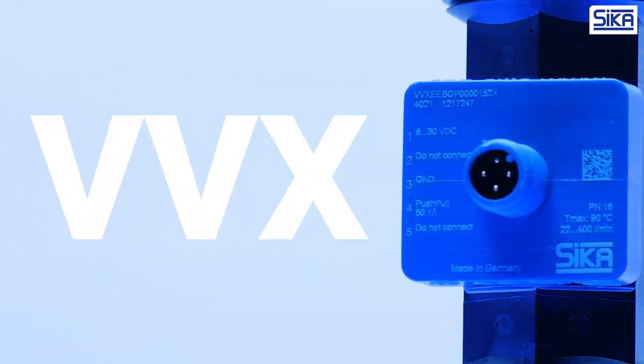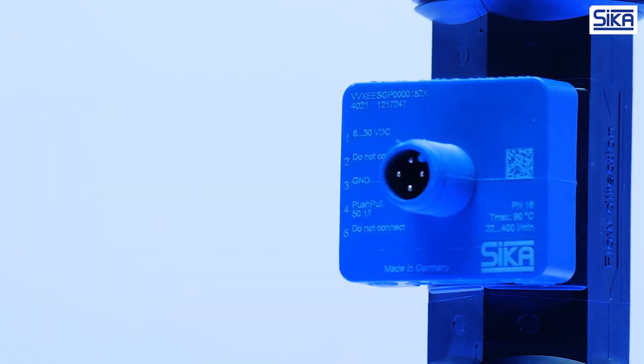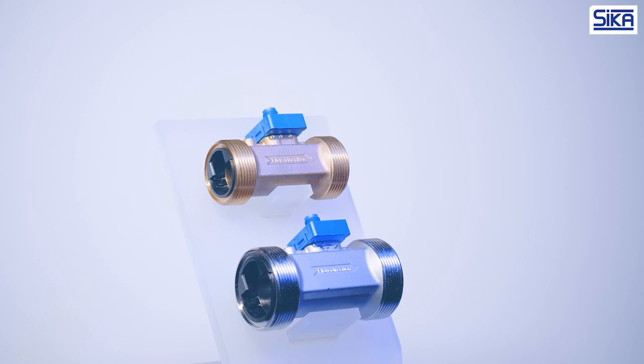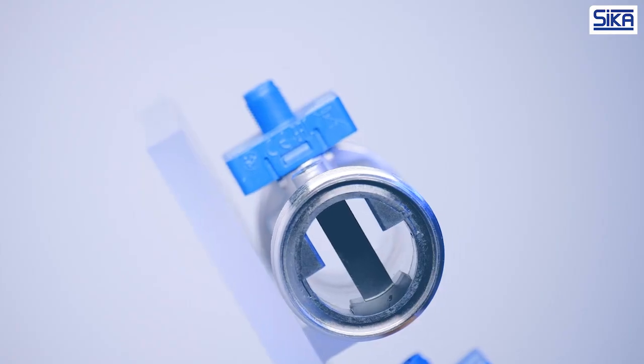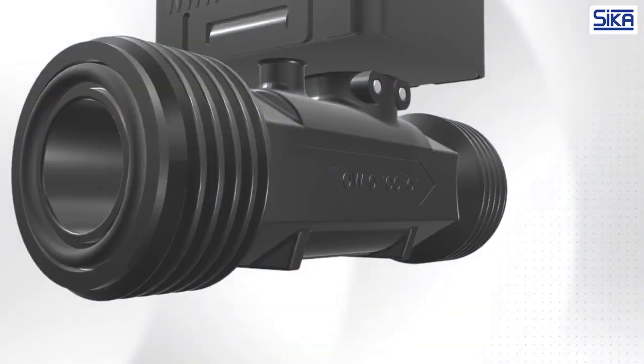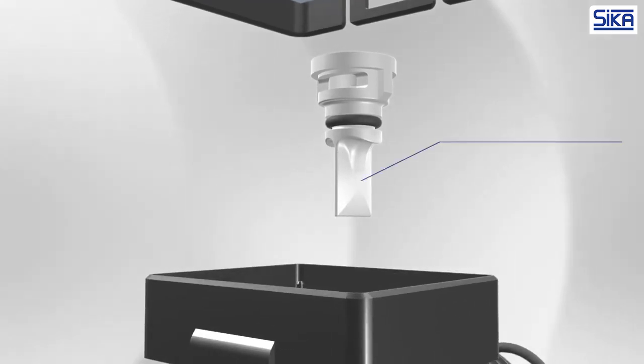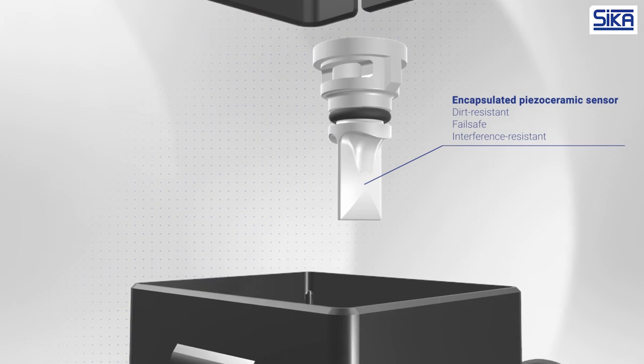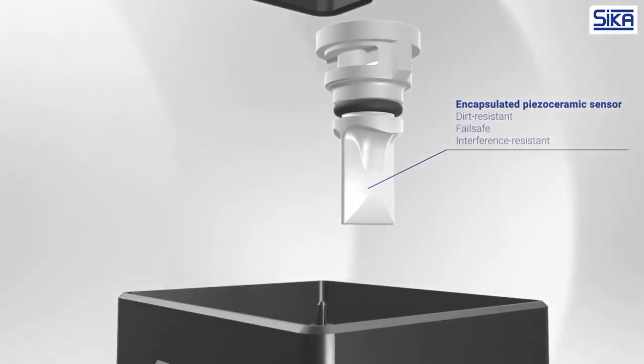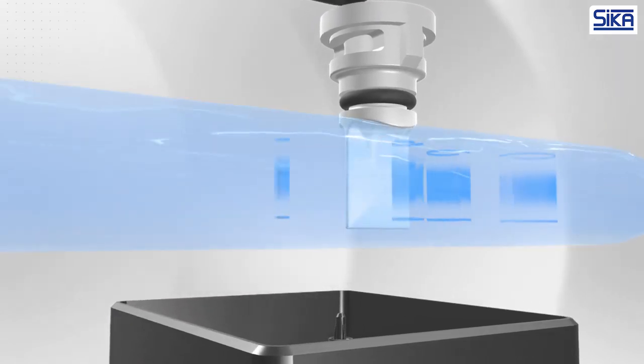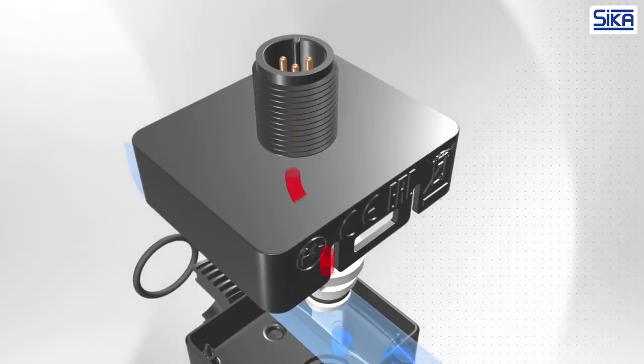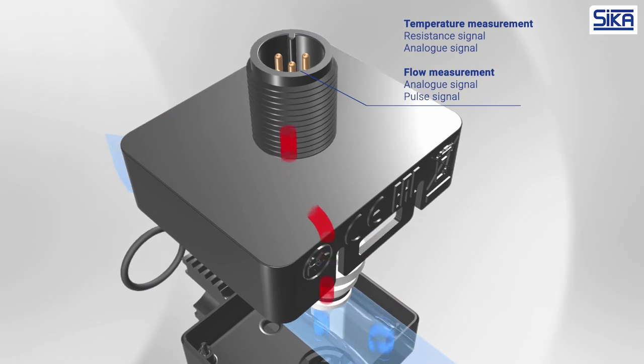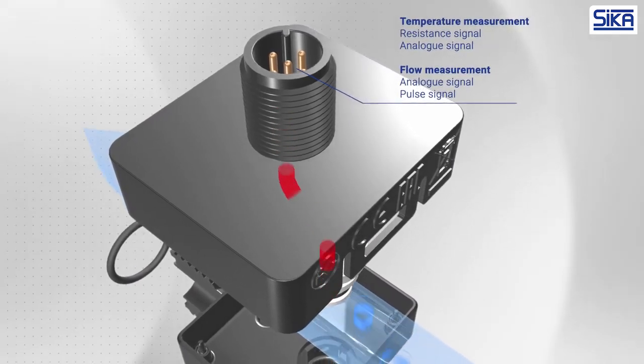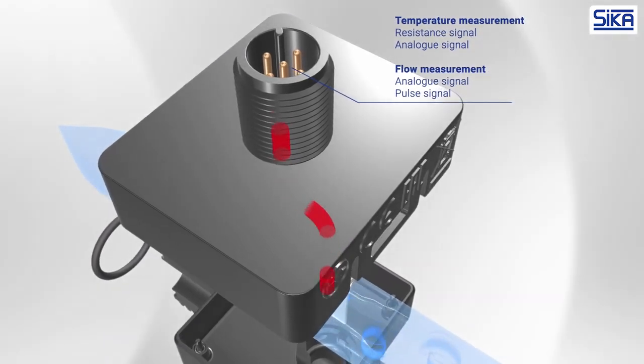One such outstanding vortex sensor is the VVX series from SIKA. In addition to the general advantages of the vortex measuring principle, our sensors are available with a housing made from either glass fiber reinforced plastic, brass, or stainless steel. These options ensure maximum durability and performance for every customer application. All SIKA Vortex flow sensors are equipped with a fully encapsulated piezoceramic sensor for detecting the vortices. This means the sensor is not in direct contact with the medium, which makes it dirt-resistant and fail-safe. This design also ensures a high level of interference resistance. This versatile sensor can also measure the temperature and can output analog signals and a pulse signal for the flow rate. A resistance signal and an analog signal are available for the temperature.